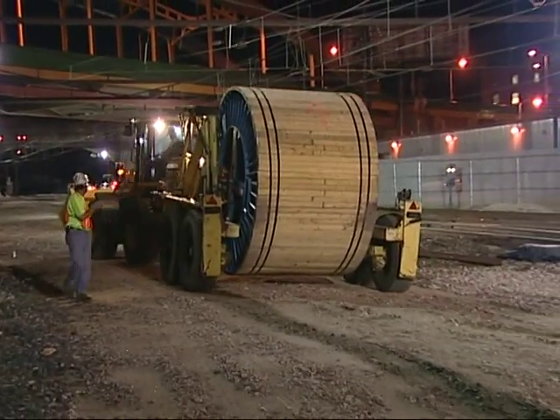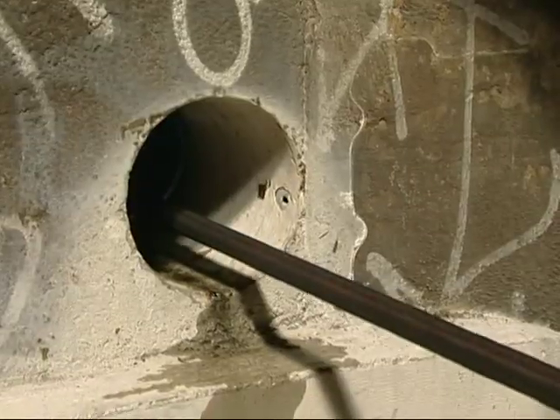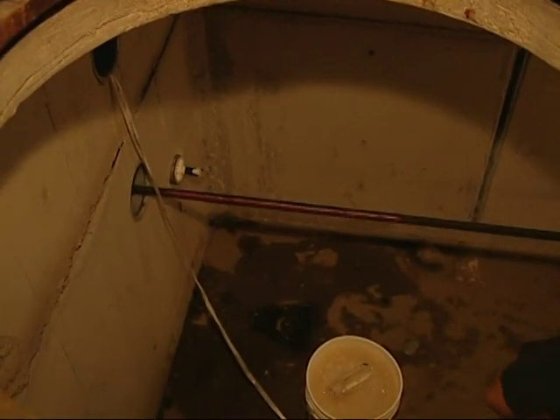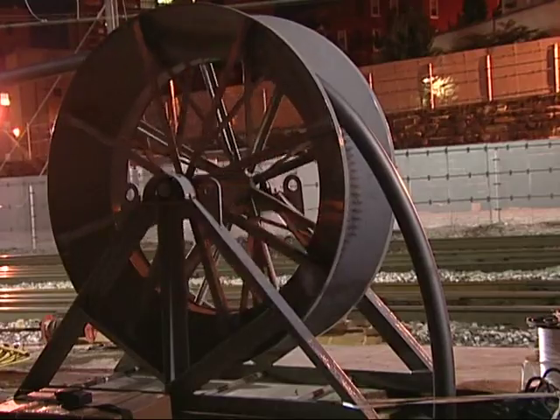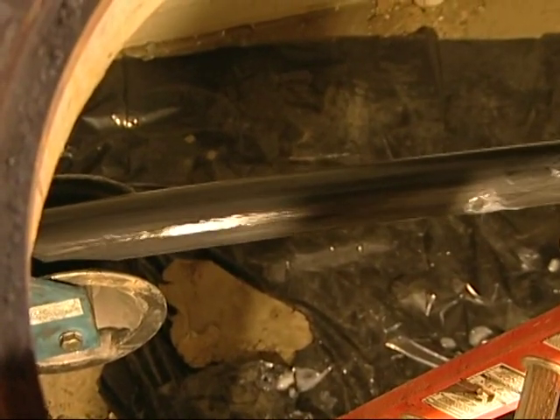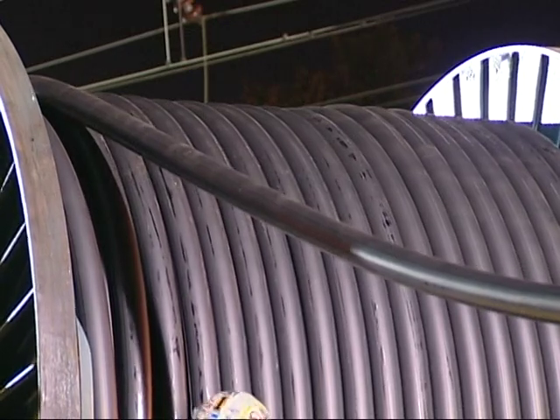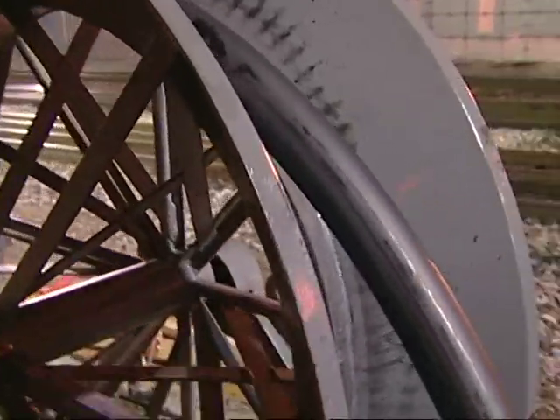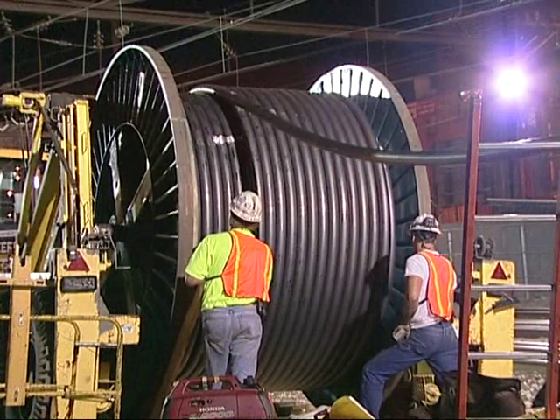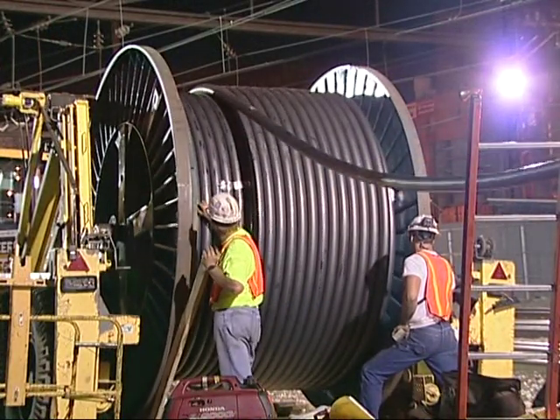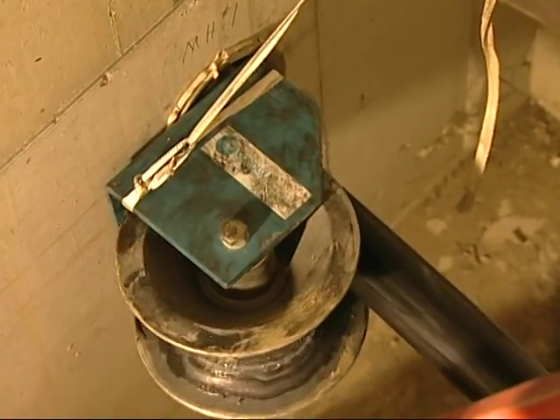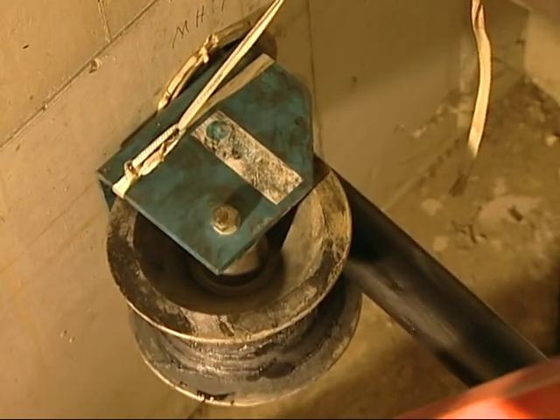We're here at manhole 8, where we're pulling in the new 121 circuit of the solid dielectric cable. You can see the cable being fed into manhole 8 and being pulled towards manhole 6 in the Wilson Street Tunnel. The conductor is about a 750 MCM conductor with about 3.5 inches of insulation around it that replaces the old oilostatic cable, which was high pressure and only about 2 inches in diameter. On completion of these pulls, we'll begin testing the cable at the end of August so we can energize and have the circuit back in service before the end of our fiscal year on September 30th.